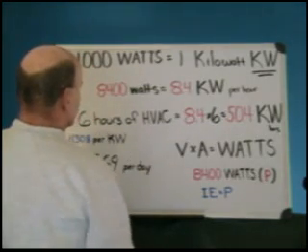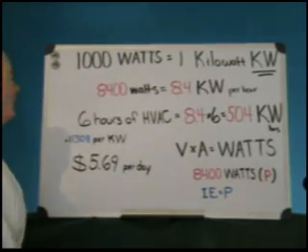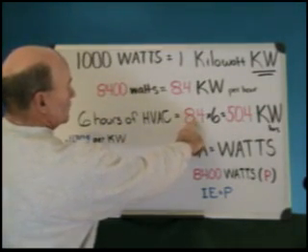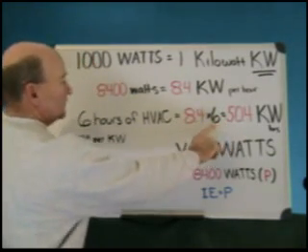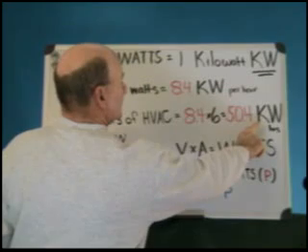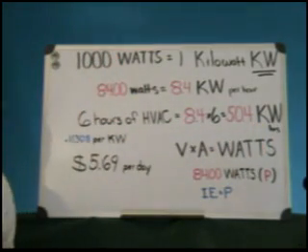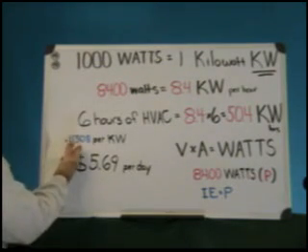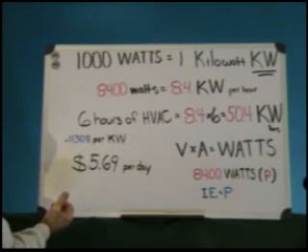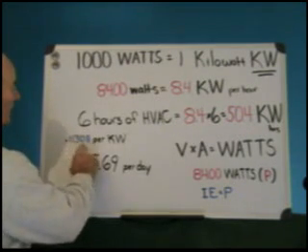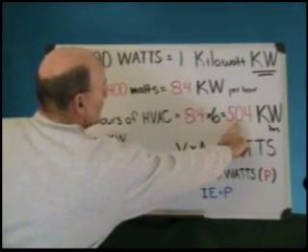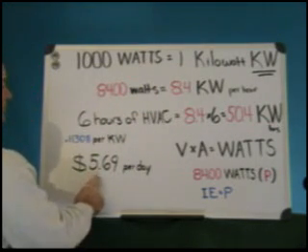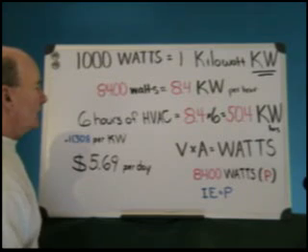So let's say you run your HVAC unit for six hours, using 8.4 kilowatt hours times six hours — that comes to 50.4 kilowatt hours. Nevada Power is charging me 11.308 cents per kilowatt hour. If you do the math and multiply that rate times 50.4 kilowatt hours, which is six hours of air conditioning, you come to $5.69 per day.